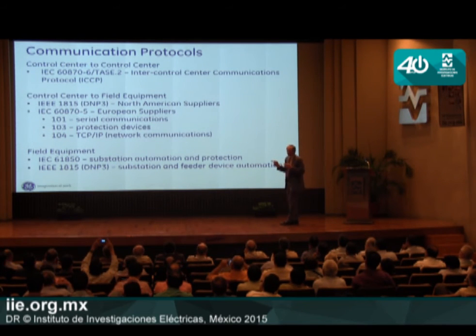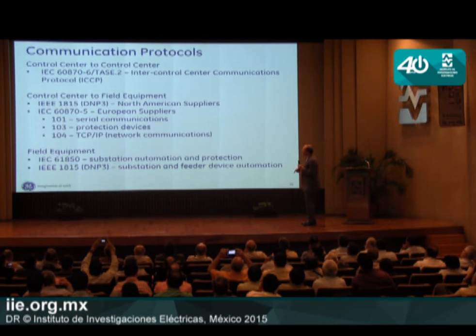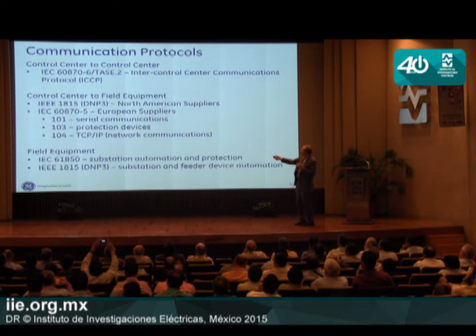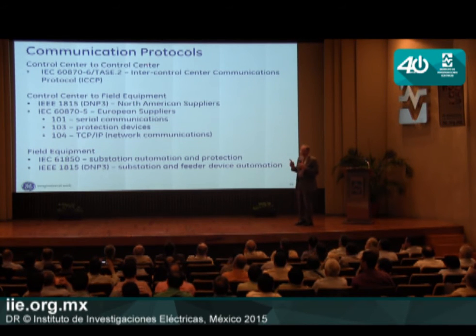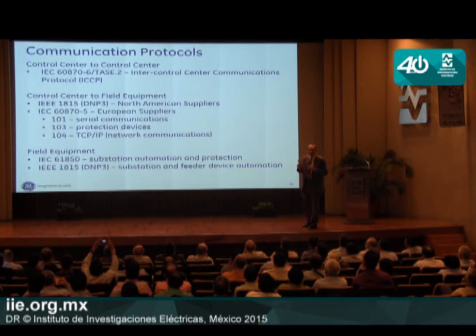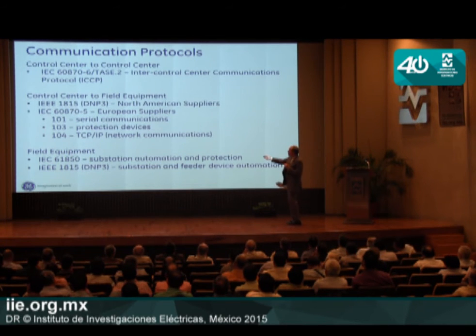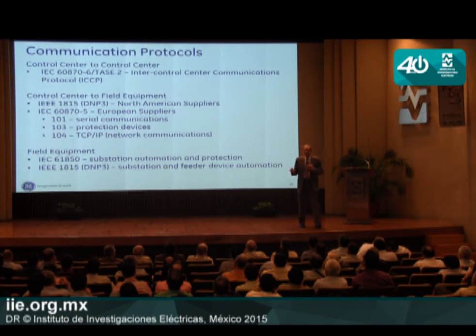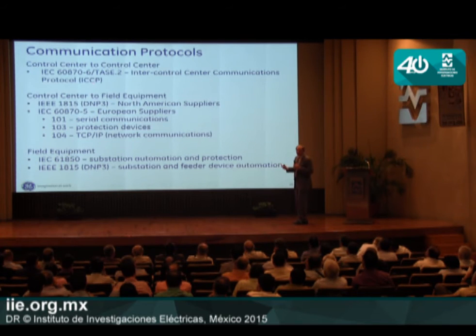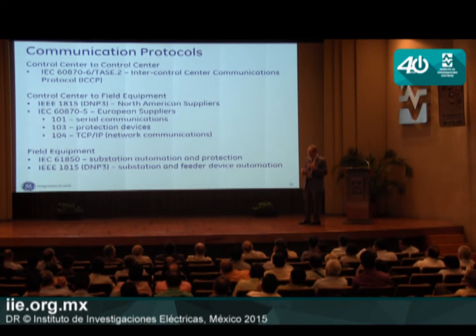This work has a lot of benefits. Today, if we want a new control center to exchange information with another control center anywhere in the world, there's one standardized way of doing it—an IEC standard also called the Inter-Control Center Communications Protocol. No matter where you are, if you buy a new DMS or EMS or SCADA system, you'll have at least one ICCP communications port. Even within a utility, ICCP is used for the EMS to communicate with the DMS.